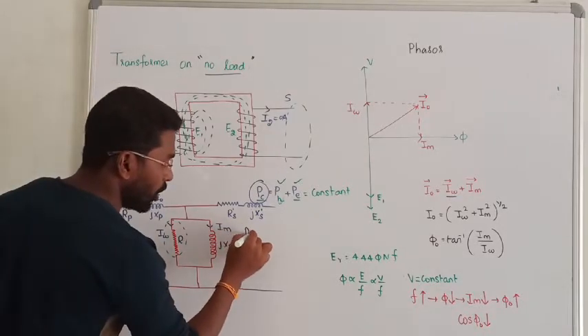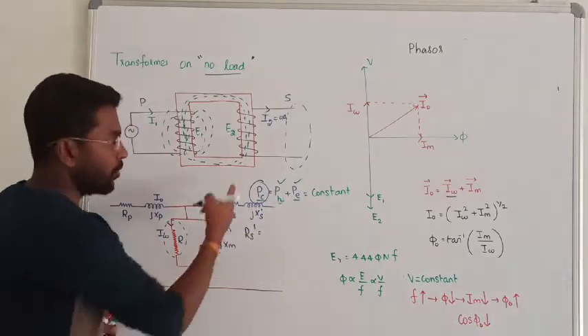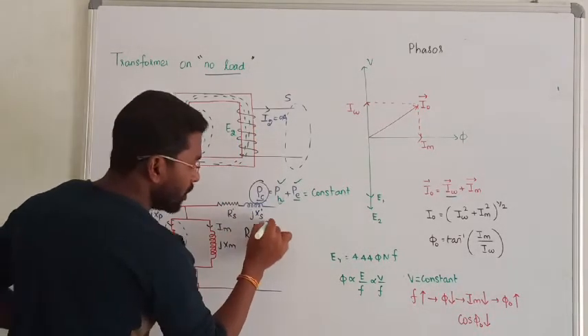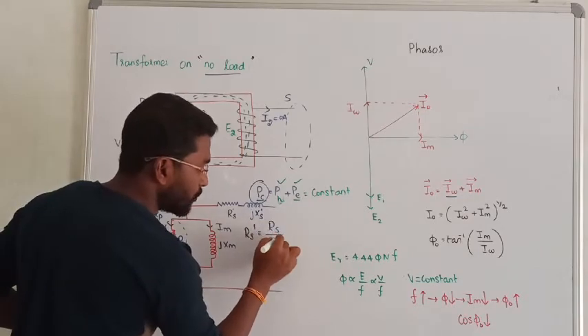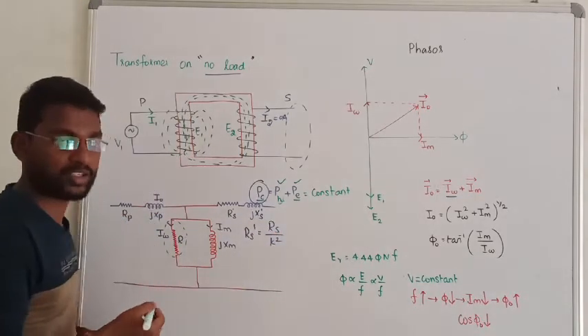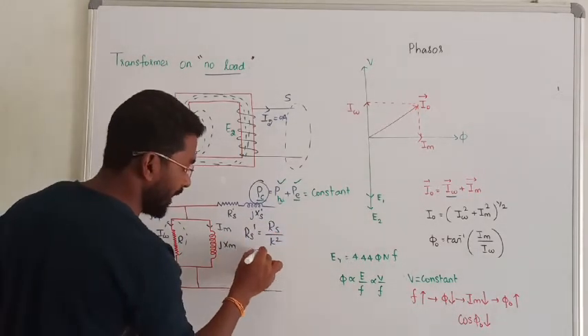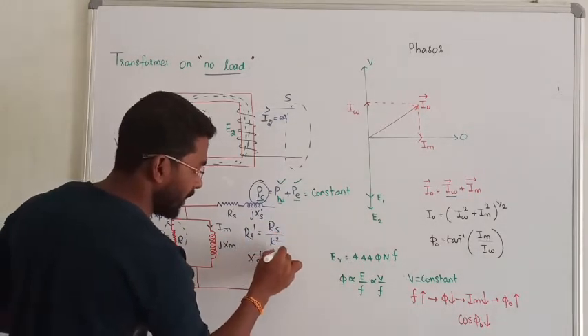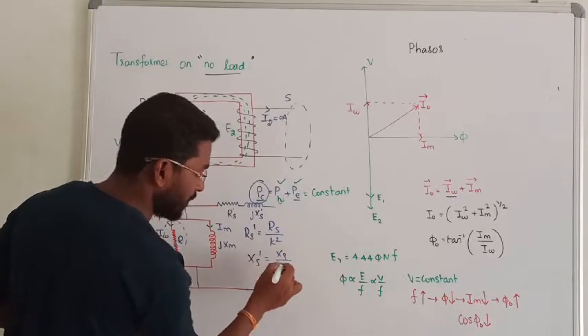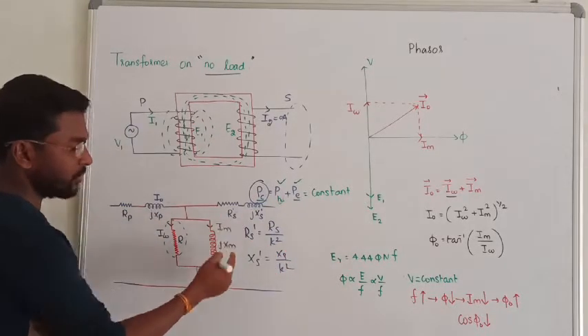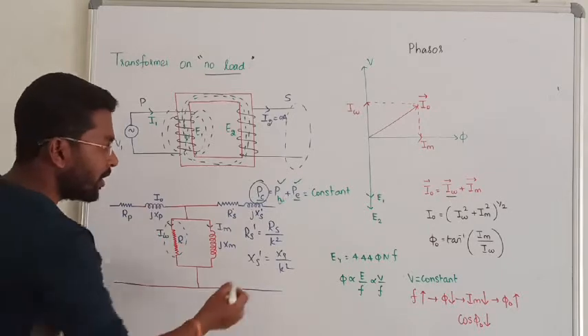To draw the electrical equivalent circuit, you divide the secondary resistance by k-squared — that is, the square of the turns ratio. Similarly, reactance is also divided by k-squared. That is how we transform secondary quantities to the primary side, giving us xs-prime and rs-prime.